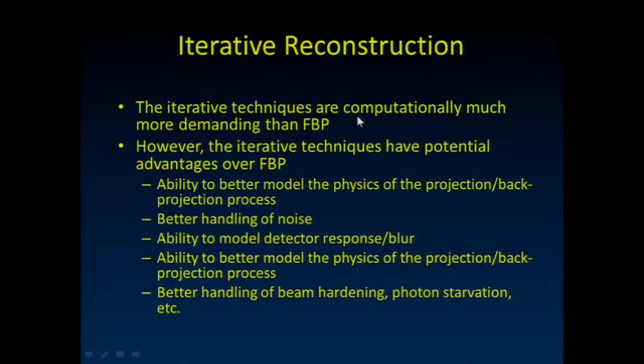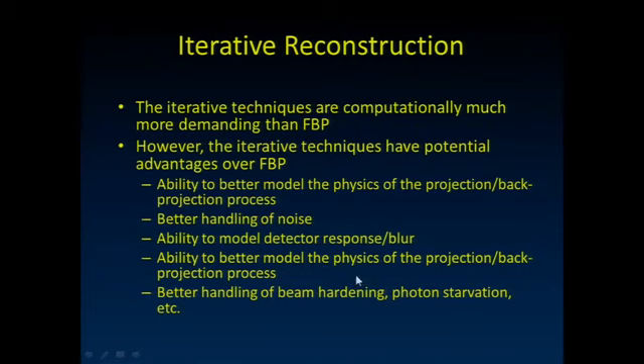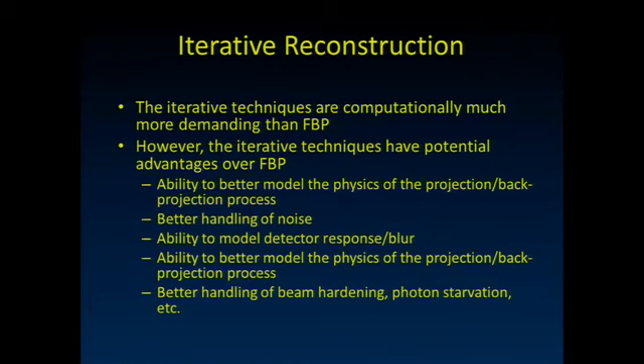Iterative reconstruction is computationally much more demanding than filtered back projection, so why use it? Because it allows us to better model the physics of the projection-back-projection process, better handle noise, model blurring in the detector, and better handle processes that actually occur but which filtered back projection assumes don't—like beam hardening and photon starvation. Iterative reconstruction is here to stay. How many people in the room have switched away from filtered back projection? There are a few hands—my guess is that percentage will continue to go up year over year.